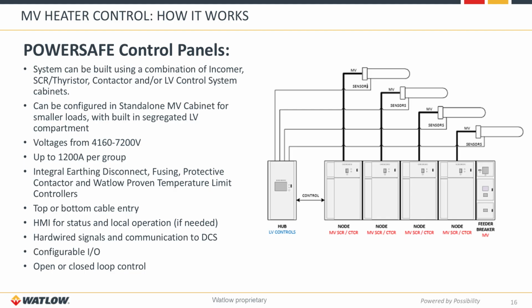Overall, the POWERSAFE control panels are configured in a very flexible and configurable type of solution. We have these node systems right here, which can be set as either a contactor or an SCR thyristor cabinet. They can be stacked together if you have a larger system with a single feeder or incomer that brings in the power and distributes that power via a busbar system throughout the entire cabinets here. If you get into a complex, very large system, we can also pull the low voltage controls out of these particular cabinets and place them into a separate low voltage control cabinet. This allows some major flexibility to your system.